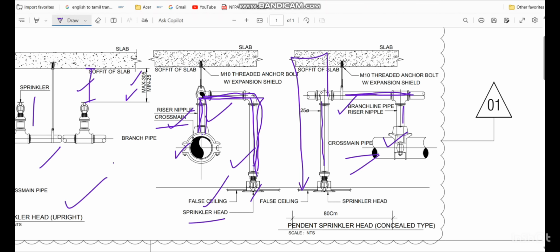And in the next case, the branch pipe we have already taken up. Then when you are taking from the branch pipe to an individual sprinkler, there is no need to provide the return bend, because normally the dust particles will settle at the bottom.